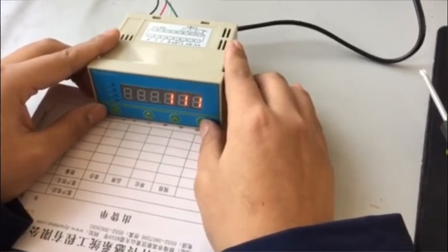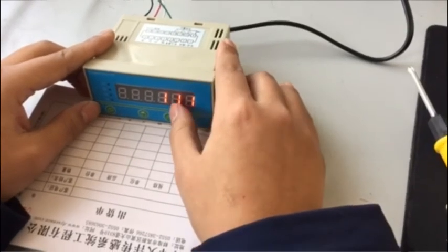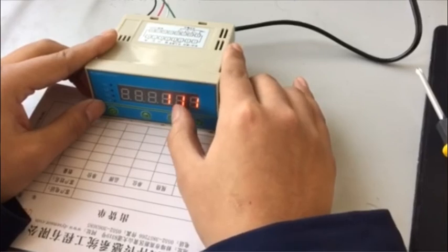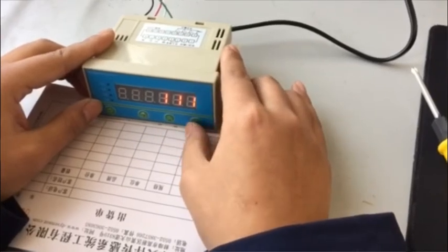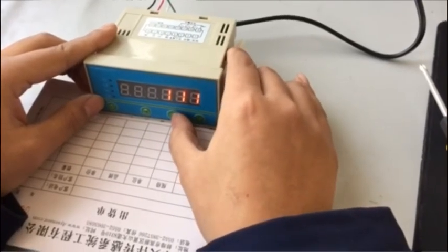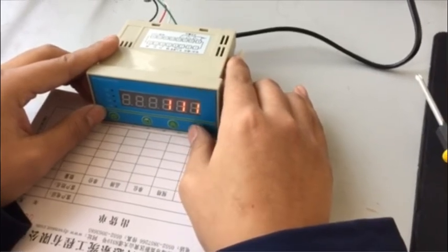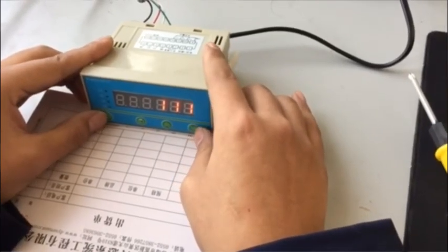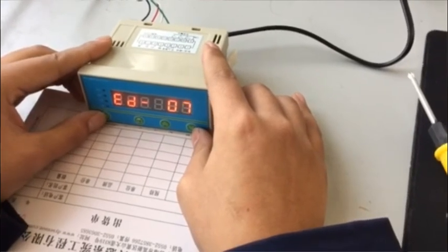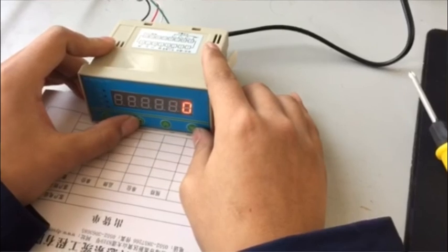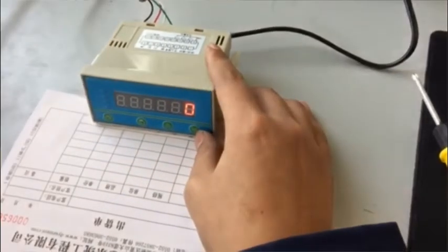ED04 is to modify the upper and lower limits. Press K4 to enter. From left to right, there are a third point alarm value, the second point alarm value, and the first point alarm value. Modify to 0, it means lower limit alarm. Modify to 1, it means the upper limit alarm. Do not modify other parameters.